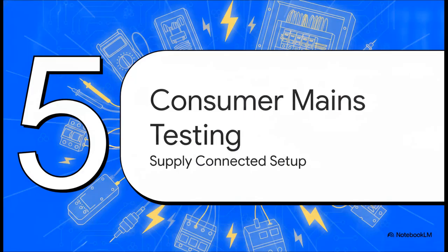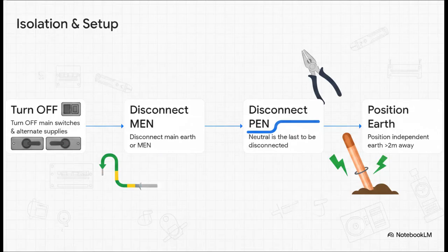Okay, Section 5, testing consumer mains procedures. This is where the theory actually hits the switchboard. During Phase 1, the isolation and setup, we first turn off all main switches. And yes, that includes those alternate supplies we just talked about. Next, turn off all circuit protective devices. Only then do disconnect the main earth, or MEN, followed by the main neutral. Did you catch that order?